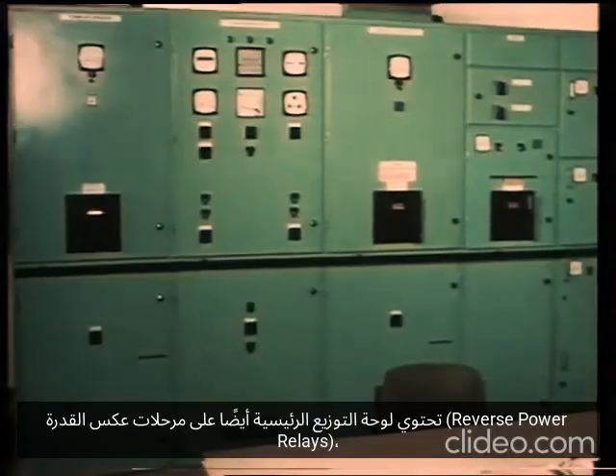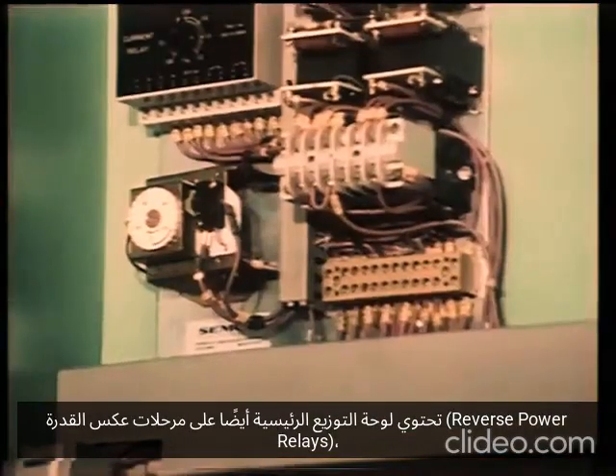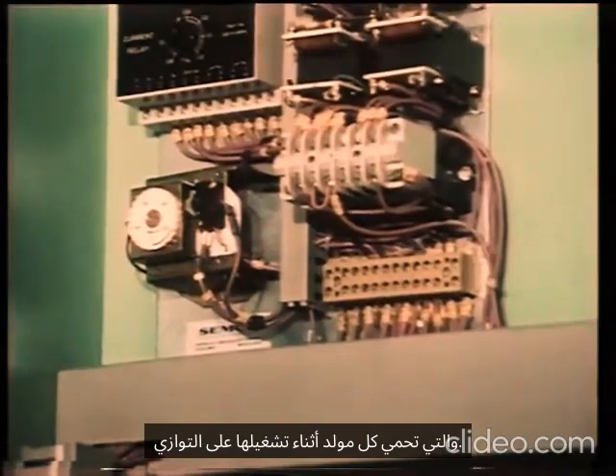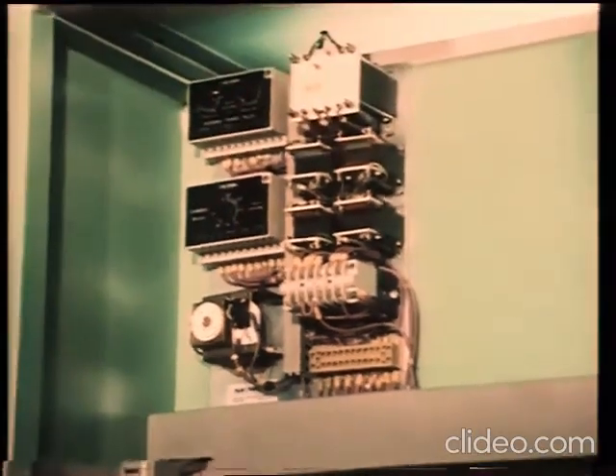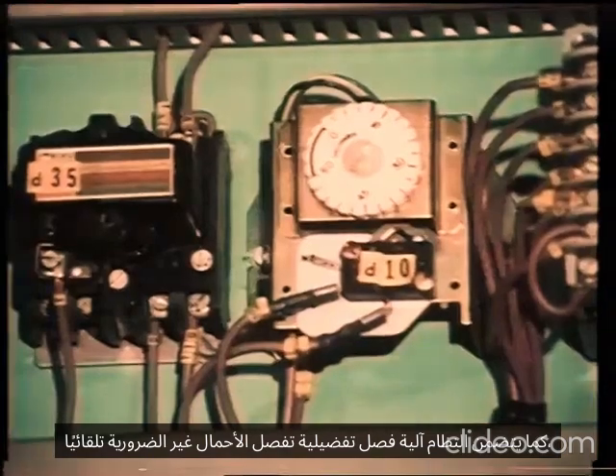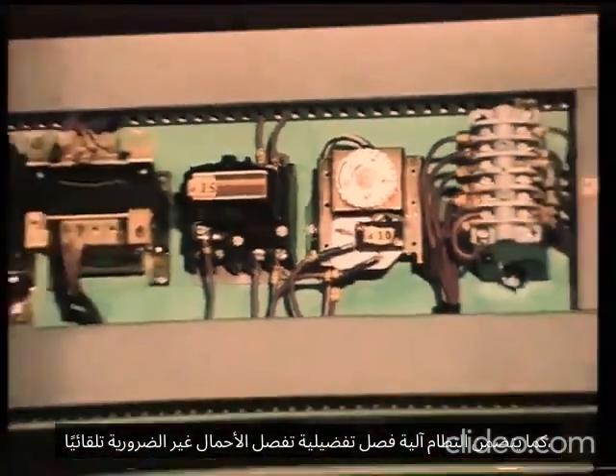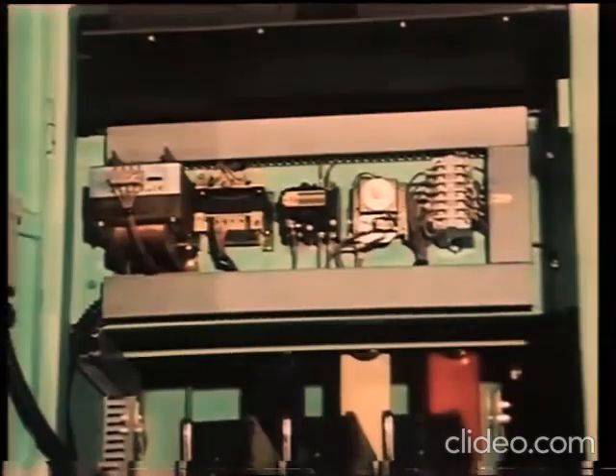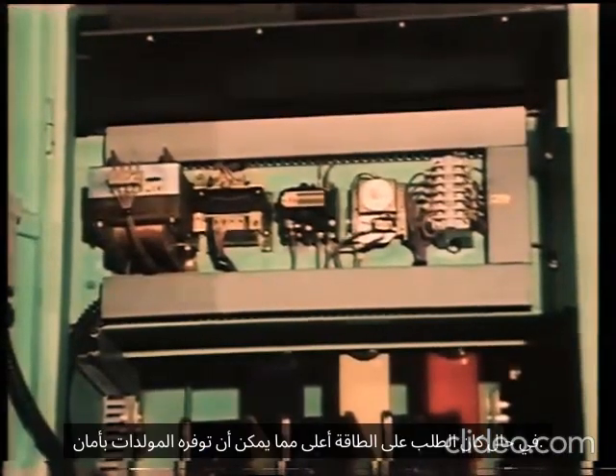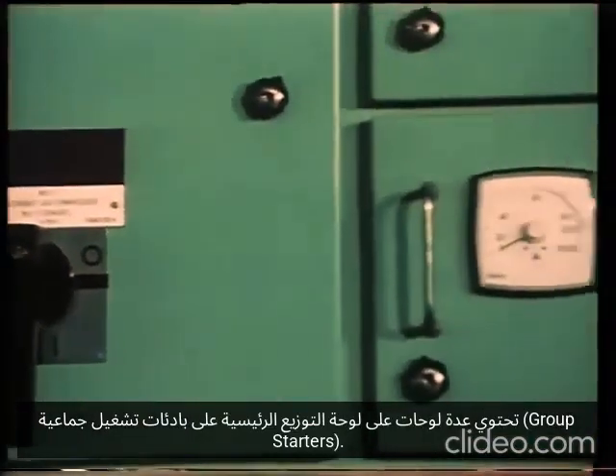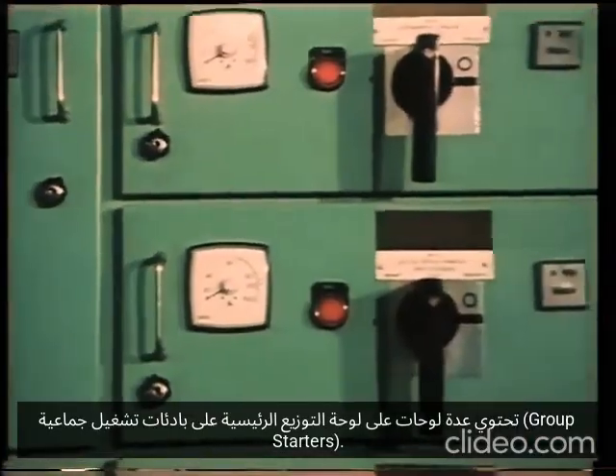The main switchboard will also contain the reverse power relays, protecting each alternator while running in parallel. Also, a preferential trip system is usually provided for tripping non-essential loads, in case the demand for power is greater than the connected alternator or alternators can safely provide. Several panels on the main switchboard will contain group starters.